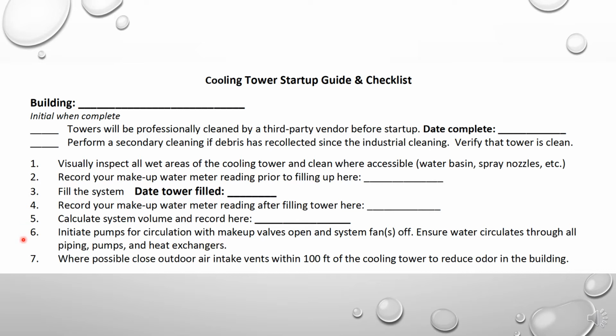And then you can initiate your pumps for circulation with your makeup valves open, but don't forget to leave your fan off. It's very important that we don't run our fan until we are sure that we have enough chemical in our cooling tower to not get anybody sick. We want to ensure that the water circulates through all of our piping, pumps, and heat exchangers. So you want to open everything up that you can.